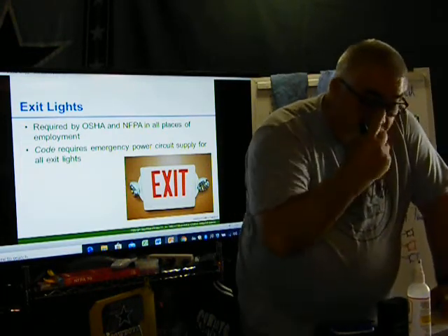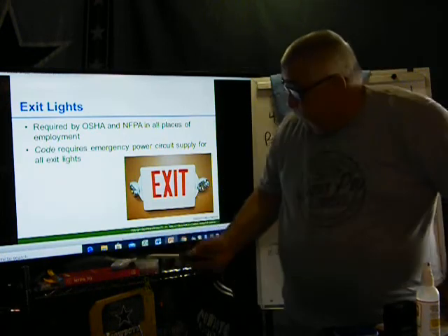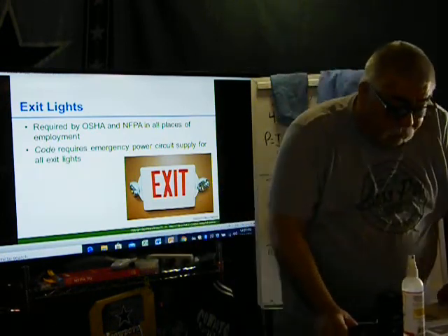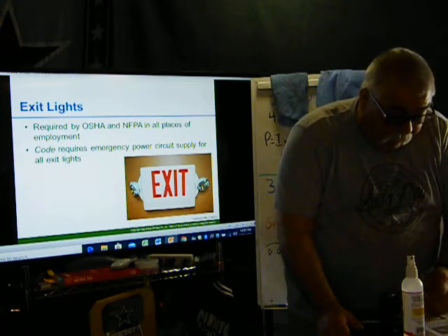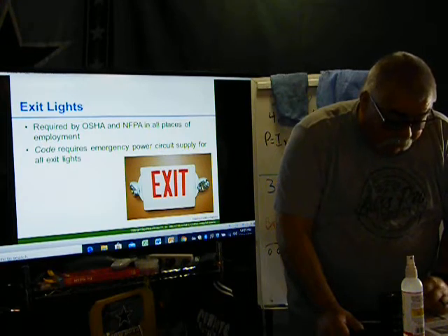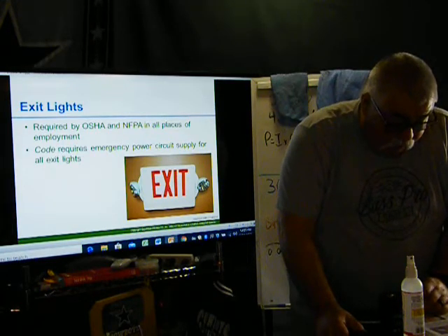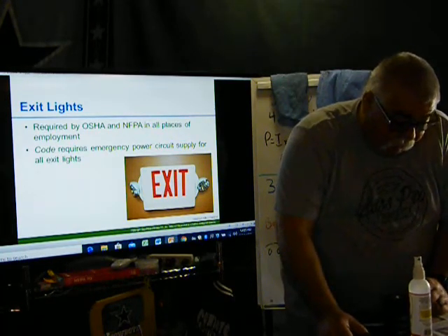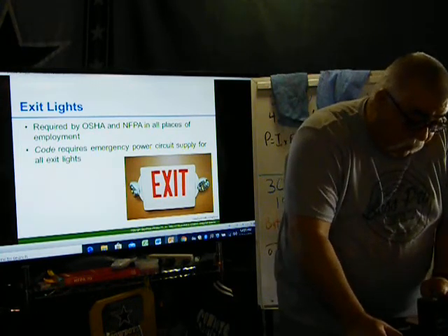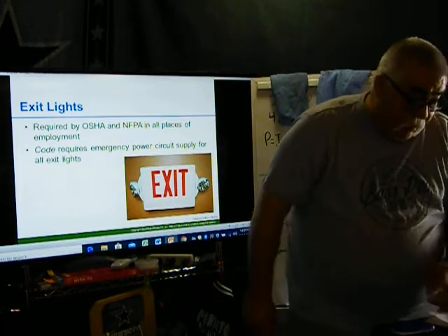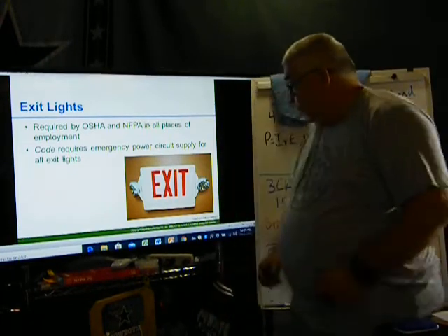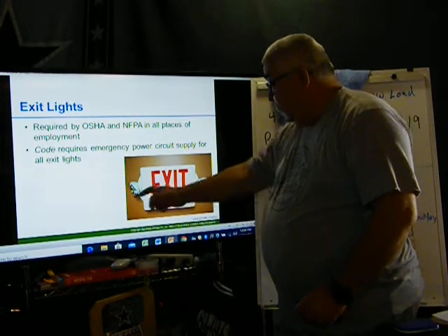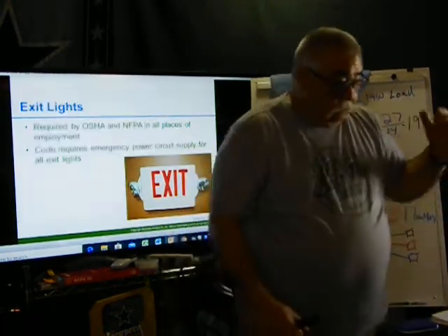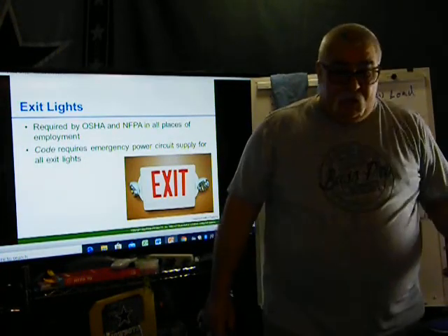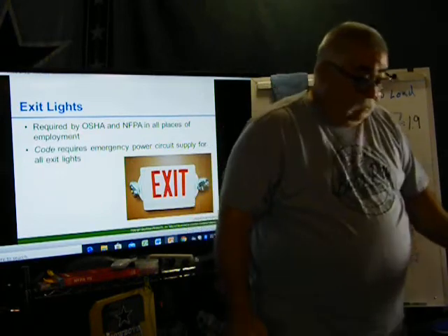So on page 217 you have the exit sign, and then you have the bug eyes that are up on top. You've got the two pictures on figure 15-16. It says battery pack emergency lighting may be plugged into any regular lighting branch circuit, provided it is not on a wall switch. In this office setting, these emergency lights are installed flush, with a drop ceiling and an LED charge light, and a test button that is easily accessible. So again, this one would have a test button at the bottom. Push the test button, the exit light would come on, and these two bug eyes would come on. Okay, so you can use that instead of an emergency power. Guess what? You've got a battery backup as the emergency power.